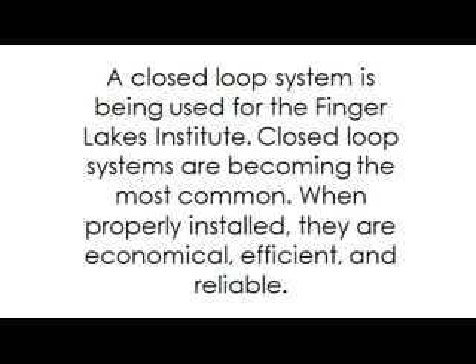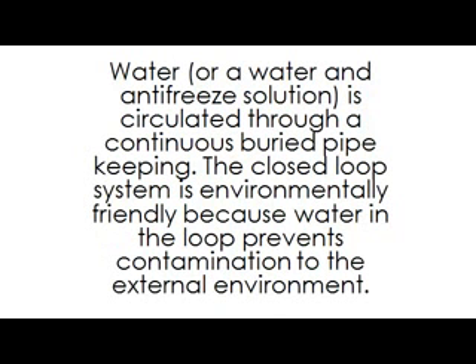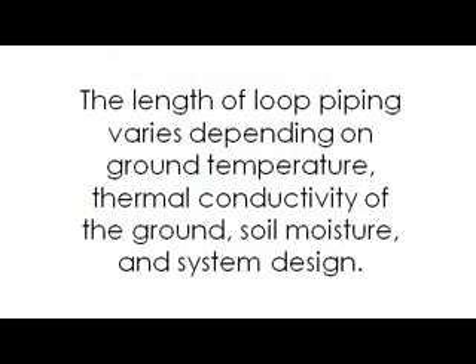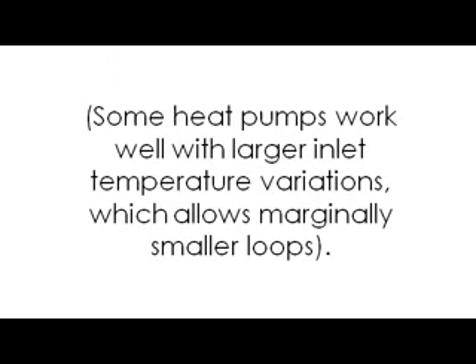A closed-loop system is being used for the Finger Lakes Institute. Closed-loop systems are becoming the most common. When properly installed, they are economical, efficient, and reliable. Water, or a water and antifreeze solution, is circulated through a continuous buried pipe. The closed-loop system is environmentally friendly because water in the loop prevents contamination to the external environment. The length of loop piping varies depending on ground temperature, thermal conductivity of the ground, soil moisture, and system design. Some heat pumps work well with larger inlet temperature variations, which allow marginally smaller loops.